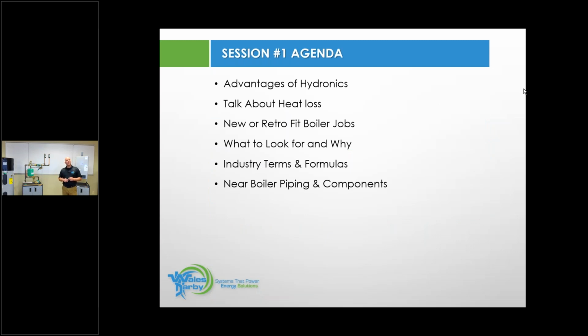So what does this course cover? Session 1, the agenda will be advantages of using hydronic heat. Anything we put water through, we consider that hydronic heat. We're going to talk about heat loss. We're not going to go into the weeds too deep on doing, let's say, a manual J. I know a lot of municipalities now are looking for a manual J calculation when you put your permits in to change out a boiler, for example. We're not going to go that deep. That would add a whole other week to our training. We're going to just stick to, we do a heat load calculation, and why do we do that heat loss calculation? We're going to stick more to that side of it.